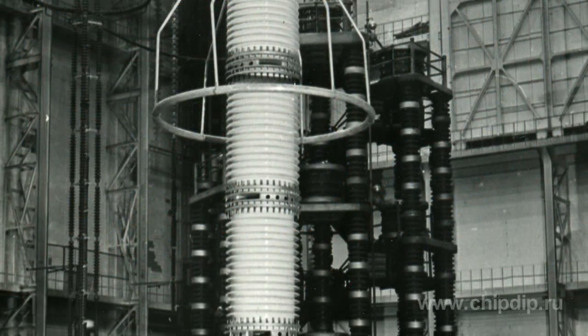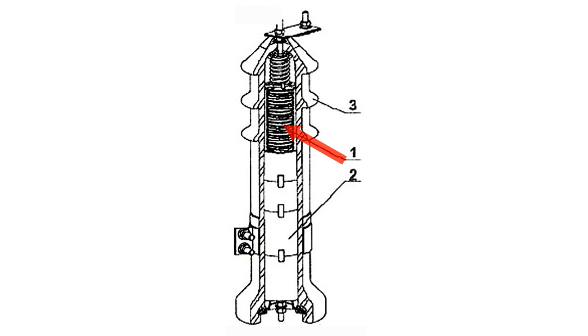One of the traditional types of power protection for equipment used in high-voltage circuits is valve-type arresters. Structurally, they represent series-connected spark gaps and varistors. Shunt resistance is switched on in parallel to spark gaps to equalize voltage along them. Spark gaps, nonlinear and shunt resistances are placed in sealed porcelain insulators, which eliminates the effect of atmospheric conditions on the characteristics of the arrestor.